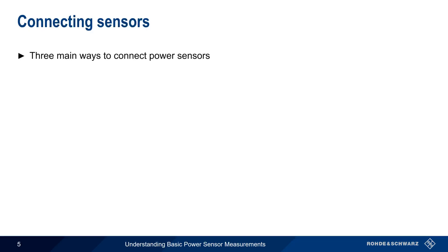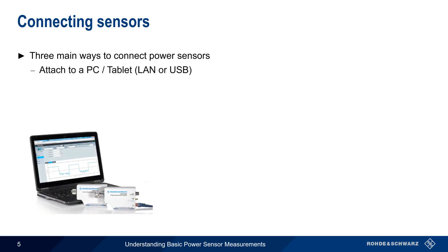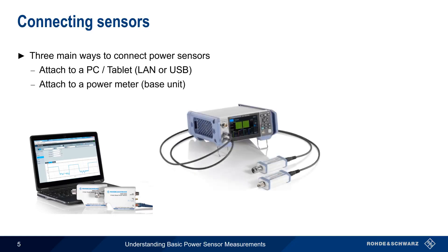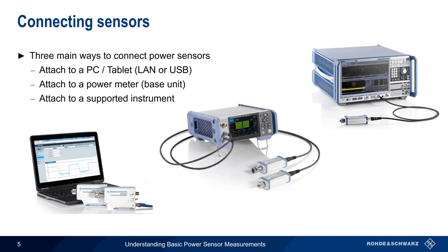There are three main ways that power sensors can be connected in order to obtain measurement results. Most modern power sensors can be attached to a PC or tablet using either USB or LAN connection, with software running on the PC controlling the sensor and displaying the results. Another common way is using a power meter base unit, a special instrument designed to connect to one or more power sensors, with built-in displays and hardware trigger capability. And some instruments, such as spectrum analyzers and signal generators, allow power sensors to be connected directly to them, with the results displayed via the instrument.